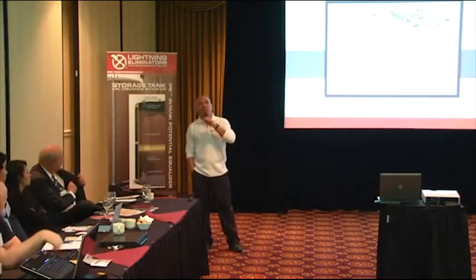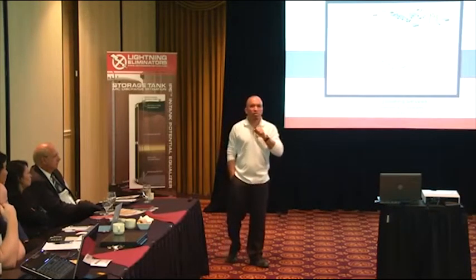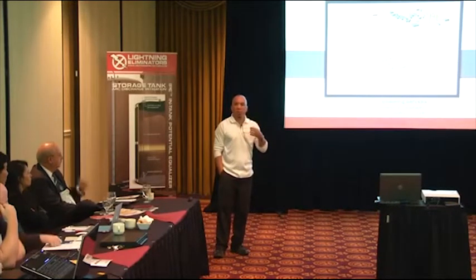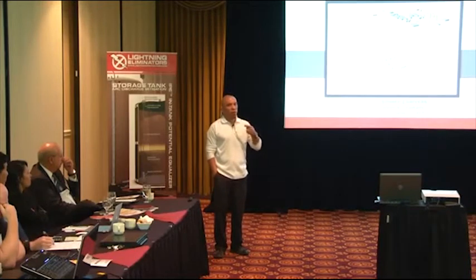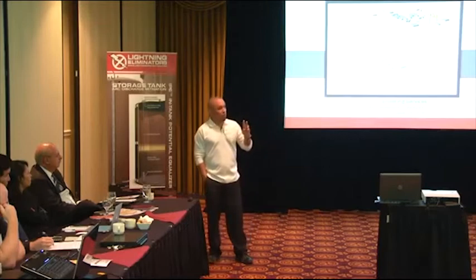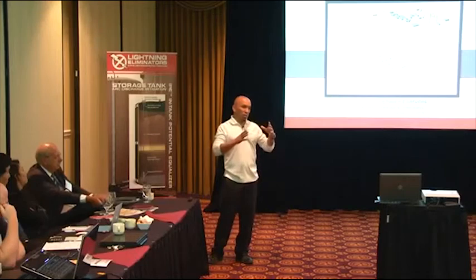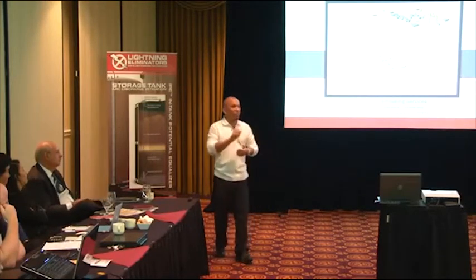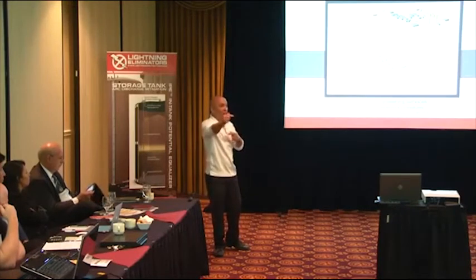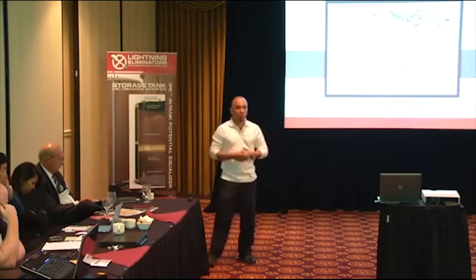Lightning Masters, I do not believe that they have the capability to do Smart Ground testing. Like I said, you'll see these other companies, they may have CDEGs and things like that. A customer may bring up CDEGs, and yes, it's well known, and actually Dr. Dawalibi and Dr. Meliopoulos used to work together. They had a falling out some years back, and I don't really know why, but the key thing there is to ask them about the meter. How is the meter removing the noise? How far away are they able to go for how large the facility is? Signal to noise ratio, all of those things.